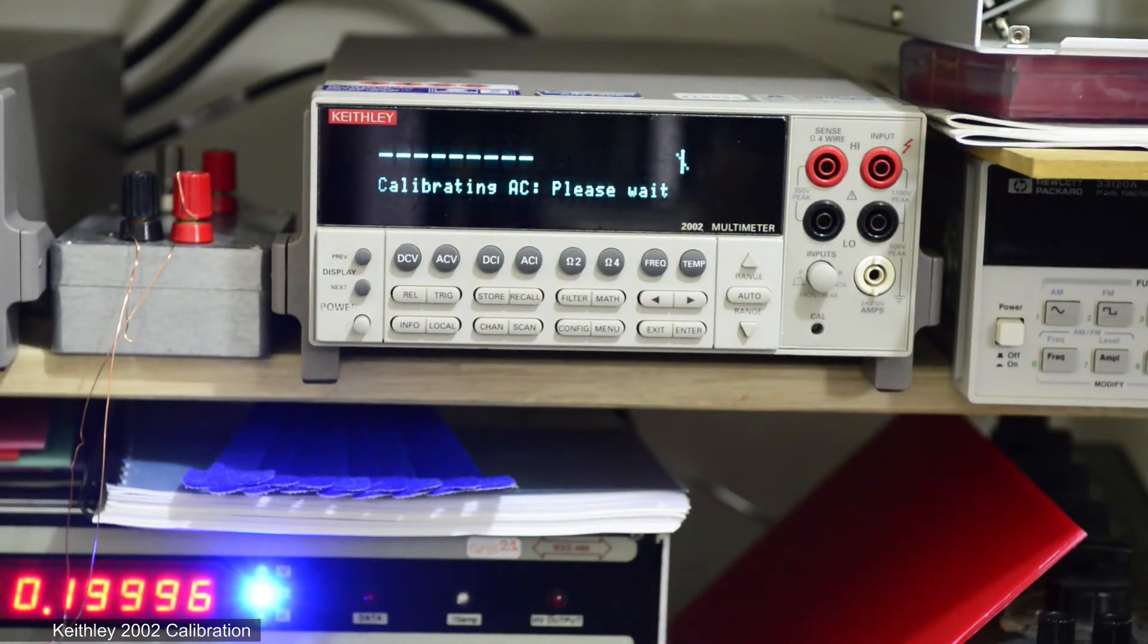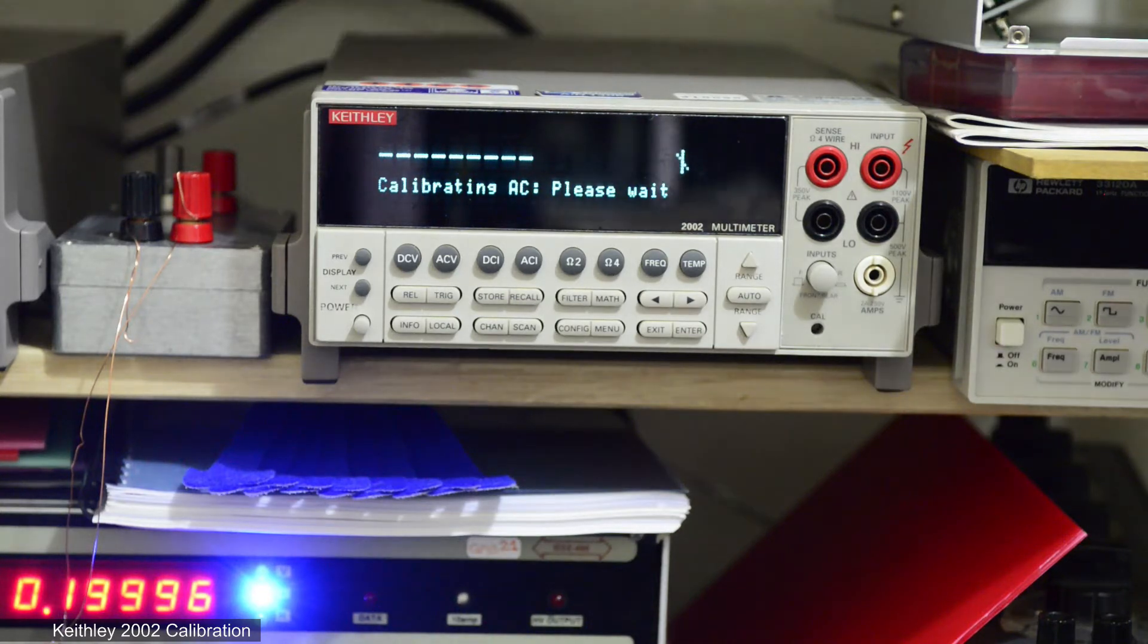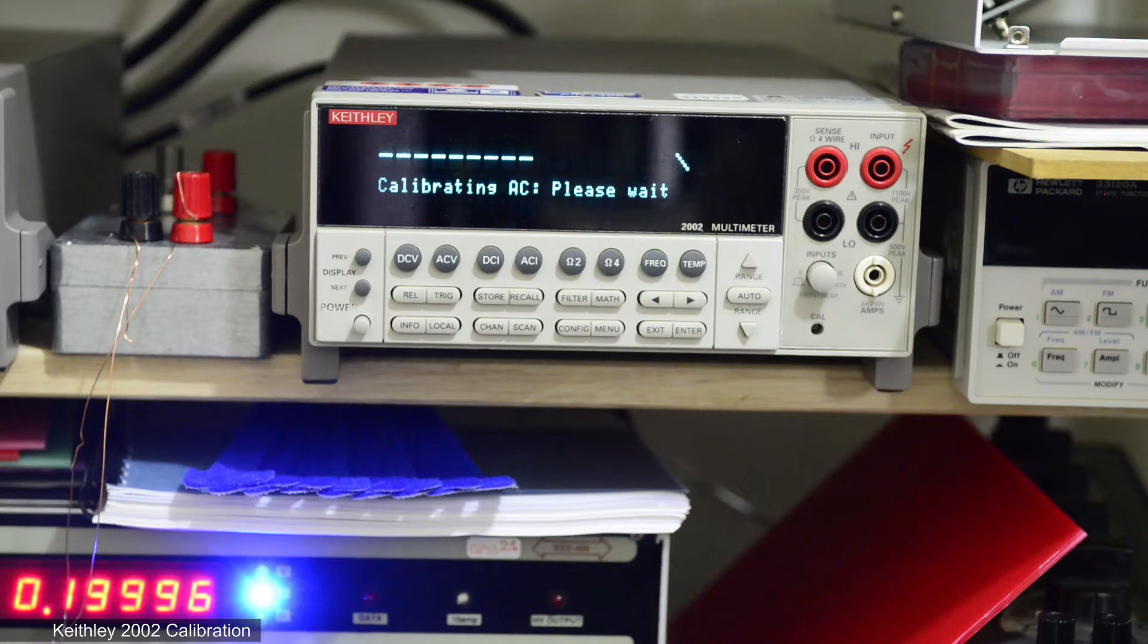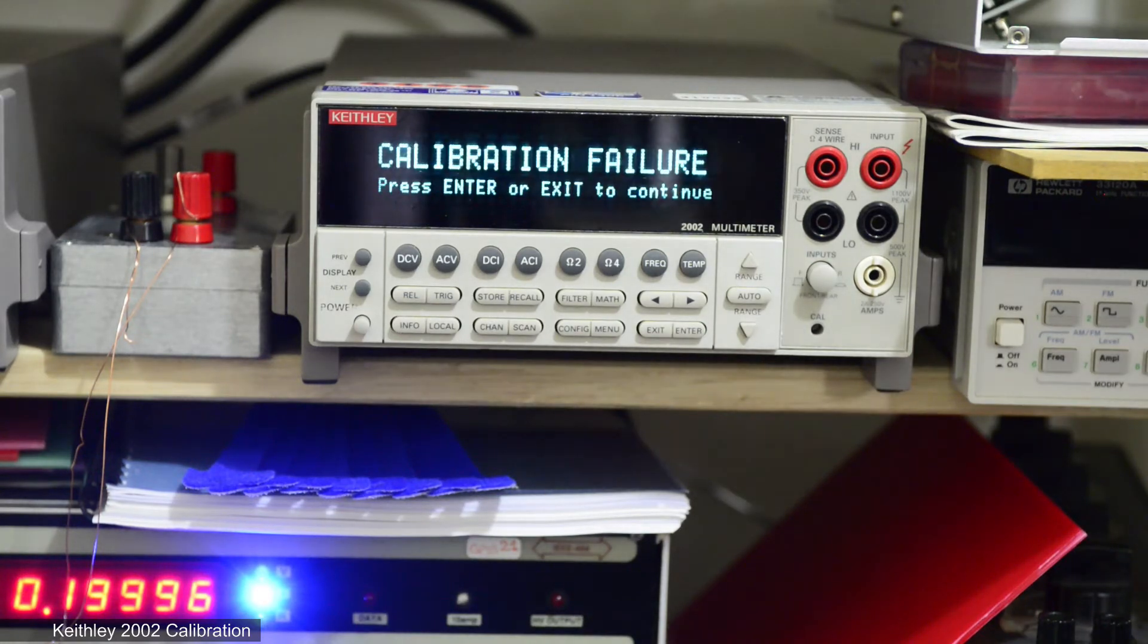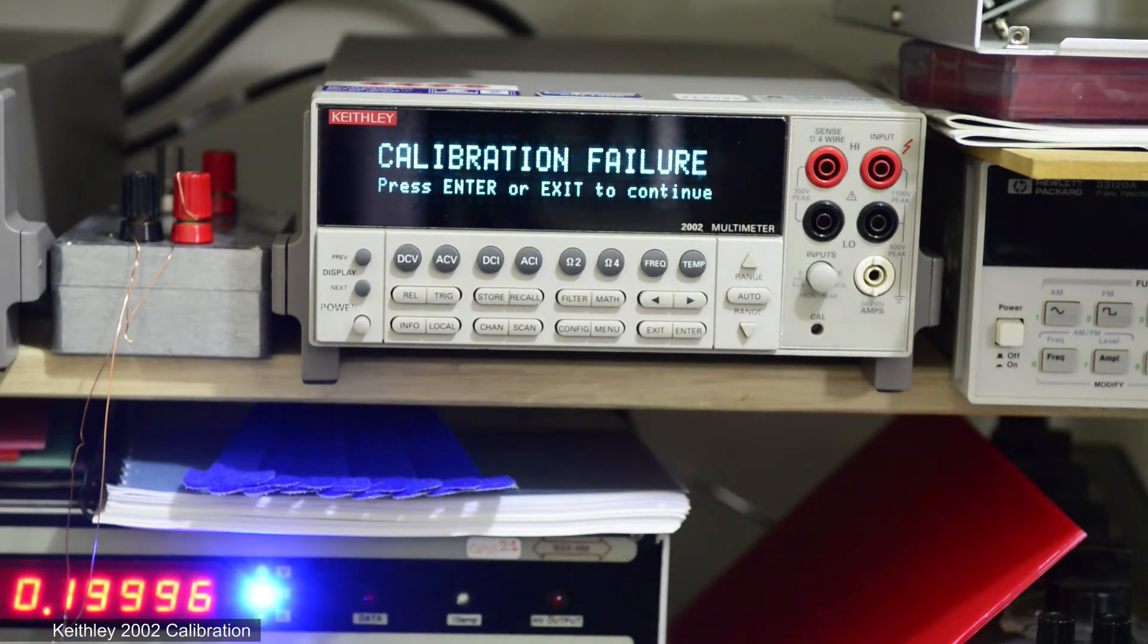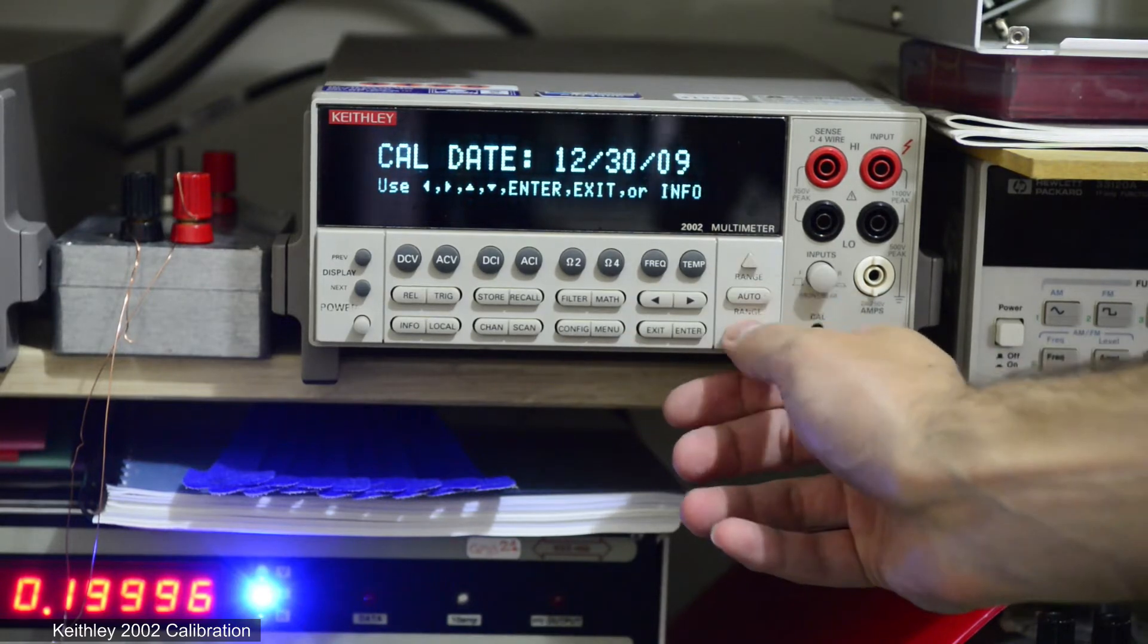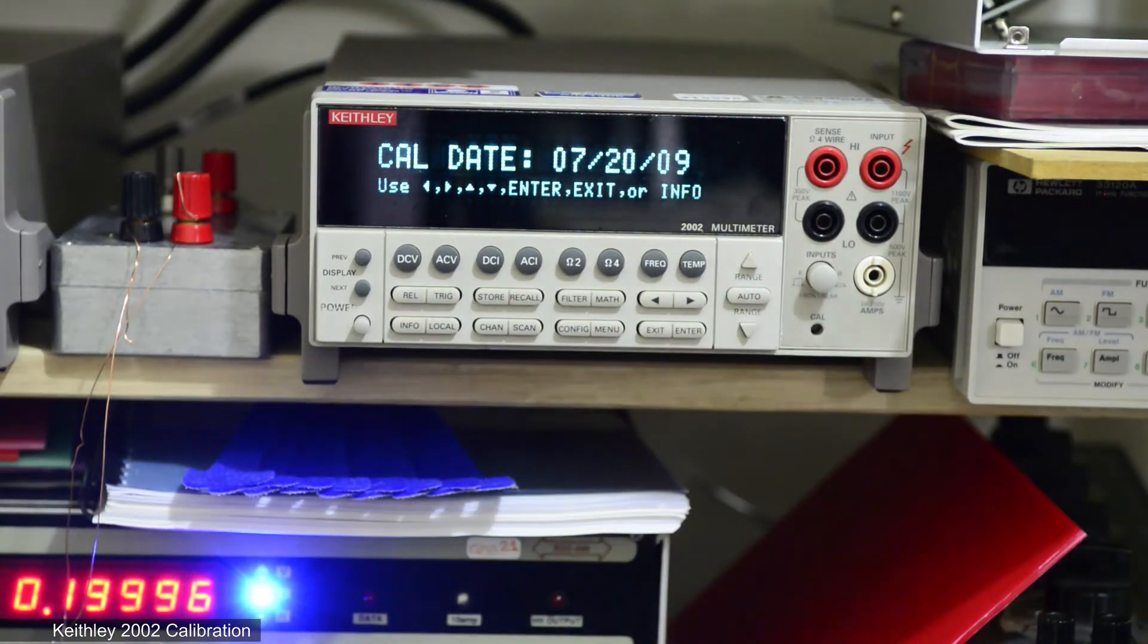the meter will take a while to calibrate its AC performance based on DC constants. If we have a few issues with current ranges, we get calibration failure. Constants are not saved into EEPROM and on the power cycle calibration will be lost.